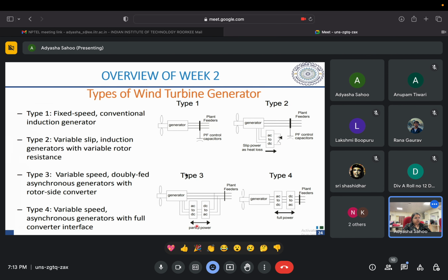Then coming to type 3, we have a DFIG, or doubly fed induction generator. We have the stator parts, and we feed the stator output back to the rotor through conversion systems to control and make this variable energy from the wind provide constant energy to the grid. So we have this conversion system.